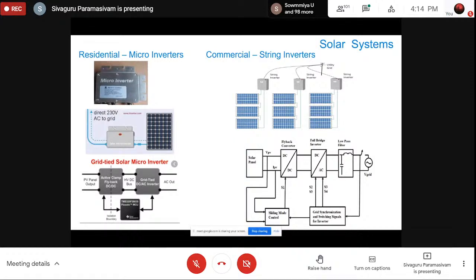The solar panel goes to a DC-DC converter, and then the DC-DC converter goes to the DC-AC converter, and then it goes to the low-pass filter. It's nothing but a filter to mitigate the harmonics, and then it's given to the grid, because we cannot pump the harmonics to the grid. The grid has a requirement that, as per IEEE 519, we should have less than 3% or less than 5% of harmonics when we are connecting power electronic equipment to the grid.